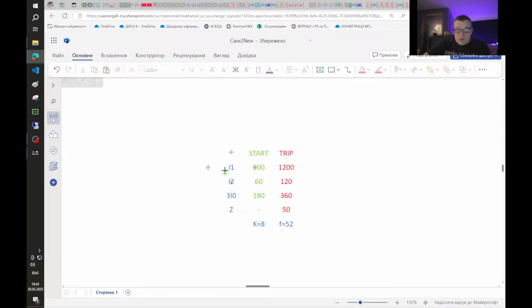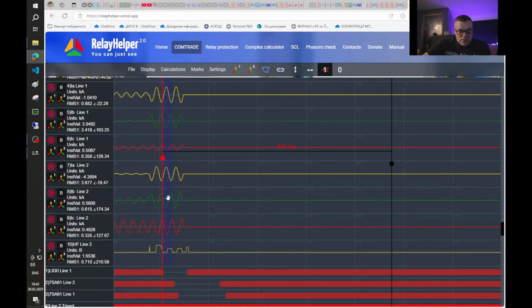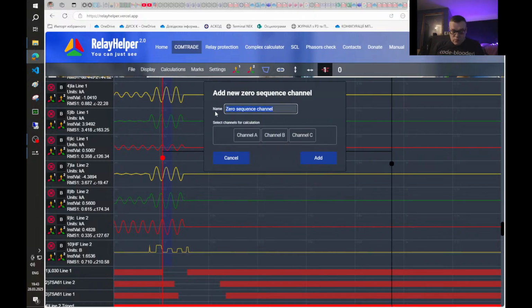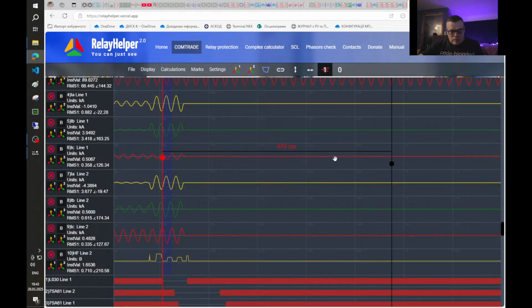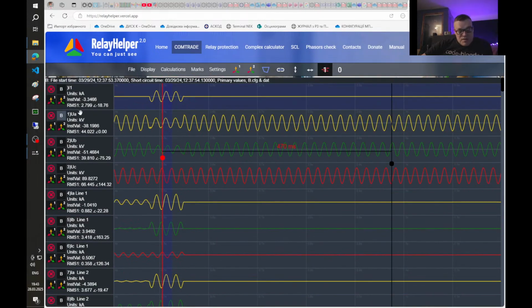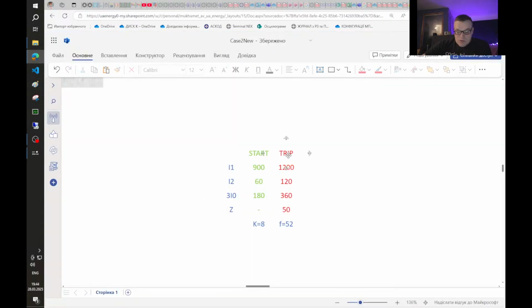So we need to calculate positive sequence, negative sequence, and zero sequence current to check it. This is related to the second line. Let's calculate it. First I'll start with positive sequence. Positive sequence is almost 2,800 amperes. So if we return to settings, already only positive current was enough to initiate trip.